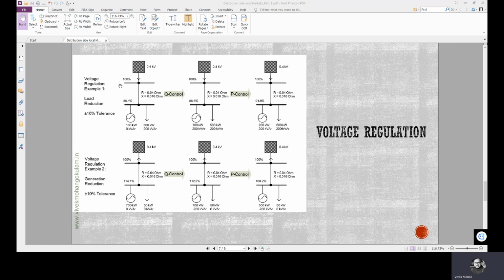First we'll see the figure on the top. So 100 kilowatts is the local generation, 500 kilowatts is the active power load, and 200 kVAR is the reactive power load. Now 100 minus 500. So basically here what happens is 400 kilowatts extra is needed from the grid side, right? 100 is already fed from the local generation. So this is the power flow direction.